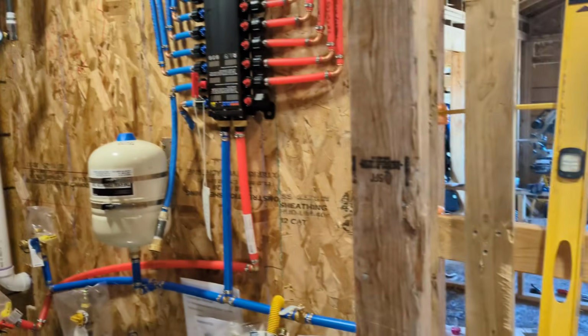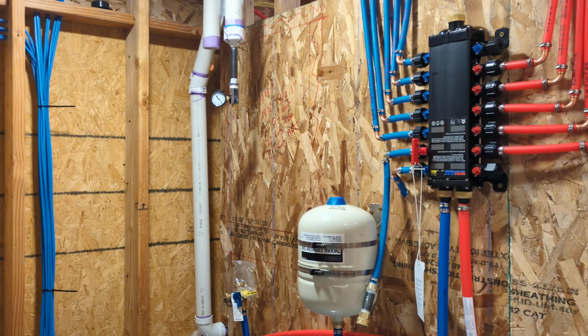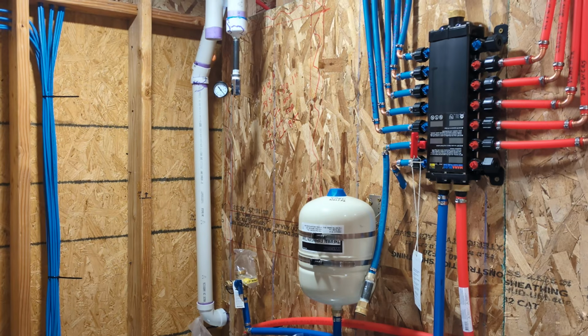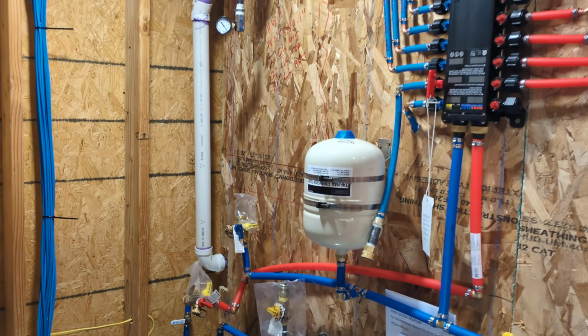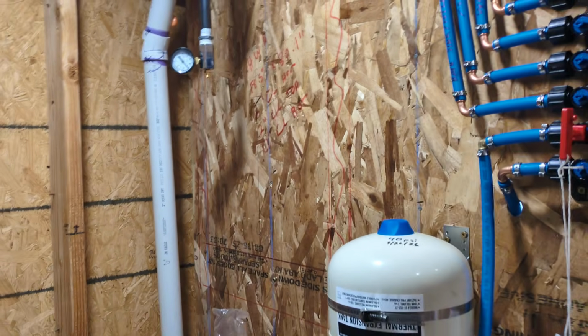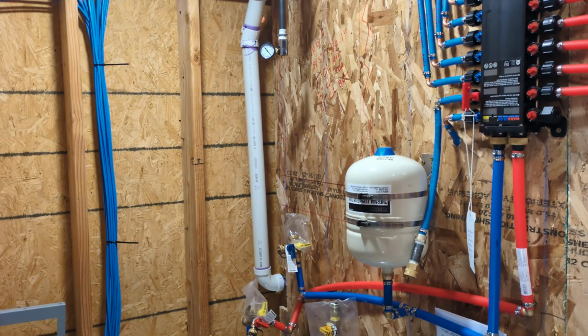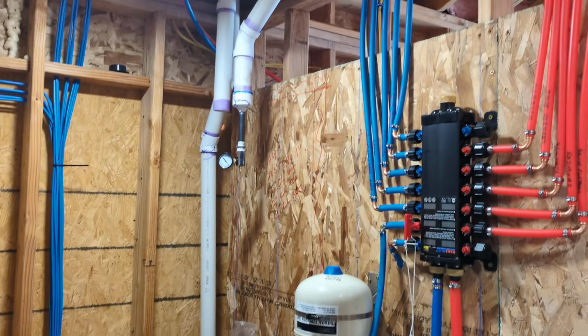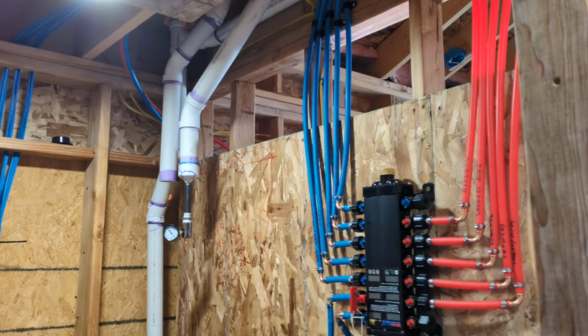Another thing they had me do is, you'll see in earlier videos that I had my water heater hung on the wall, and they asked me to remove it because they wanted me to do a pressure test. So this is now leaked down since I did the test, but it was holding pressure when the guy came in. It only needs to hold it for 15 minutes, but you need to do a 5 psi pressure test on the exhaust side of your water heater piping.